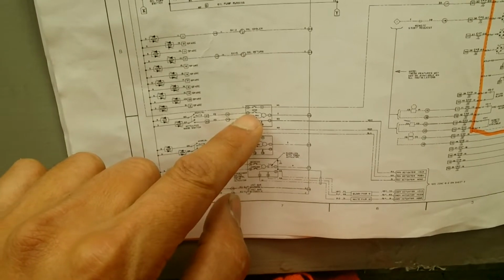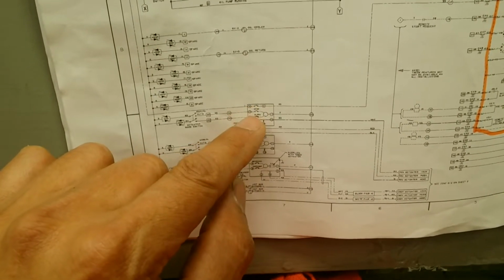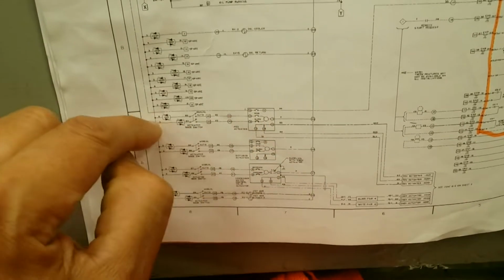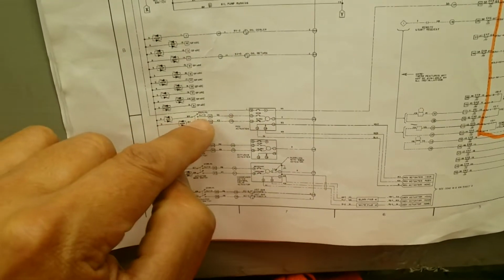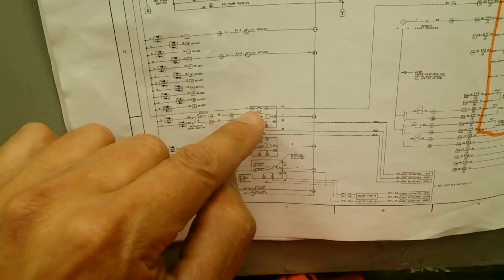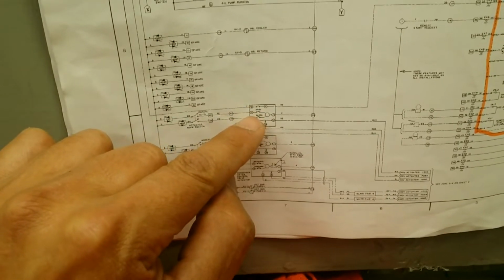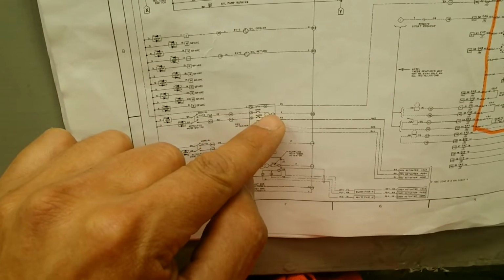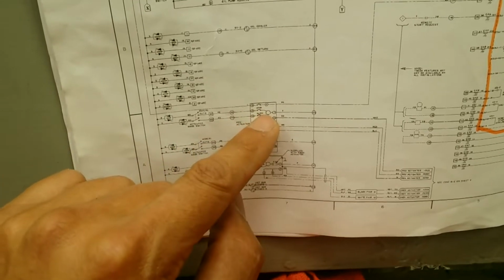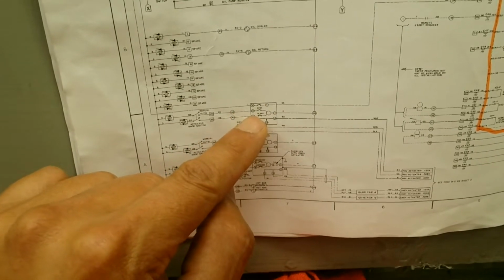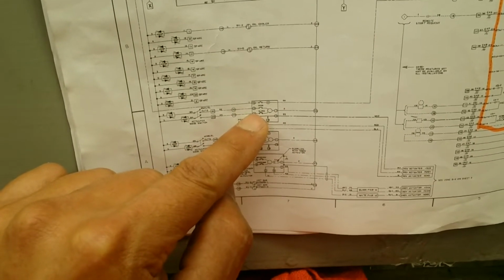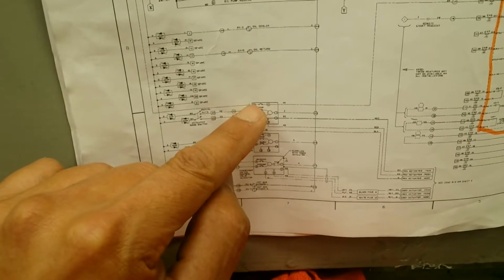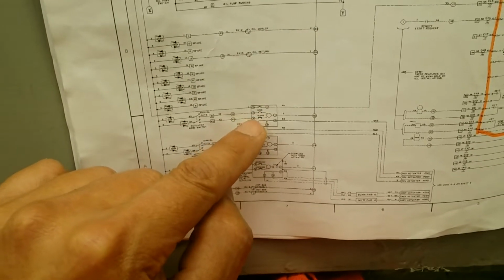And if you never get 115 volts between that point and this point, that means that the SSR or the switch is just not doing its job. If you get 115 volts between this point and the valve wouldn't open in that case, then the problem is at the valve. Same thing for testing for the close command. You just simply put your multimeter between 1 and terminal 3 of the valve.